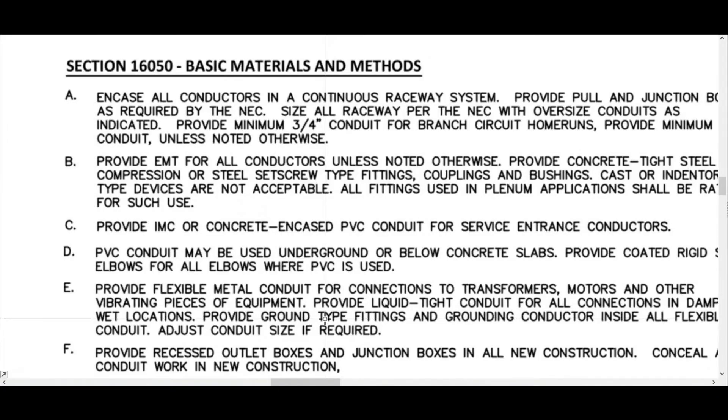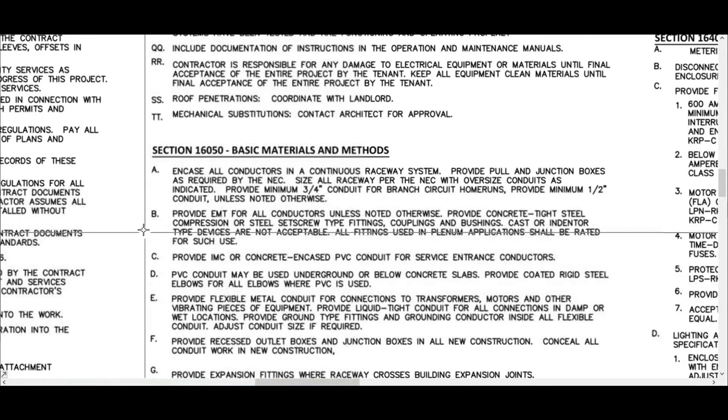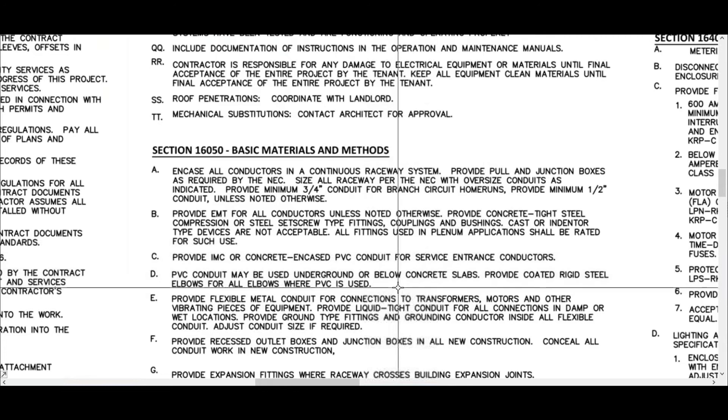See this section 16050. It says: encase all conductors in a continuous raceway system, provide pull and junction boxes as required by NEC. Let's jump down to PVC. This is important to know for estimating: PVC conduit may be used underground or below concrete slabs. Provide coated rigid steel elbows for all elbows where PVC is used. That's super important because those PVC coated rigid elbows, when you get up to 2, 3, and 4 inch, can be a lot of money. These specs are full of information that you need as an electrical estimator so you estimate correctly and don't leave things out.